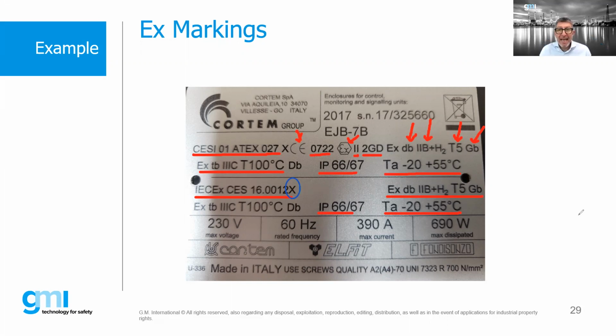Bob. Oh, and Paulo just circled the little X. What does that X mean? Yes, and that's a good question. So X is a very, very important thing that we should all look for. And what that means is that the product has what is called a condition for safe use. So if we find products, one of the most important things is to make sure that we pull the certificate. And that IEC EX certificate is actually located on the IEC EX website at iecex.com. We can pull this certificate, and on that certificate, it'll say something about what the conditions for safe use are.